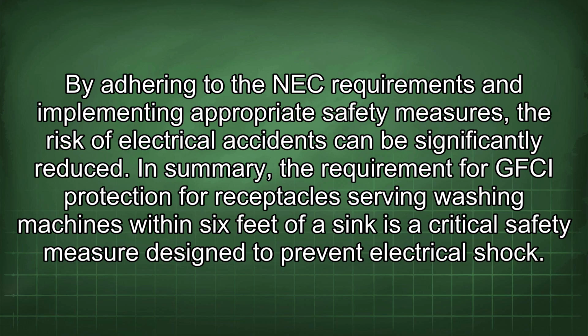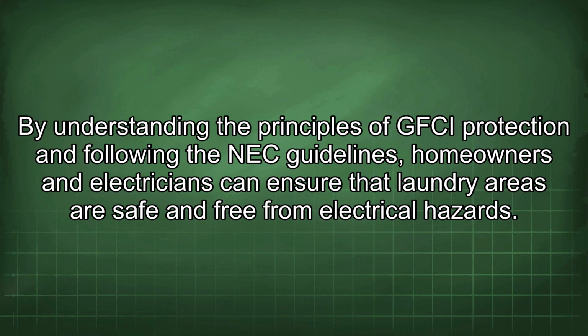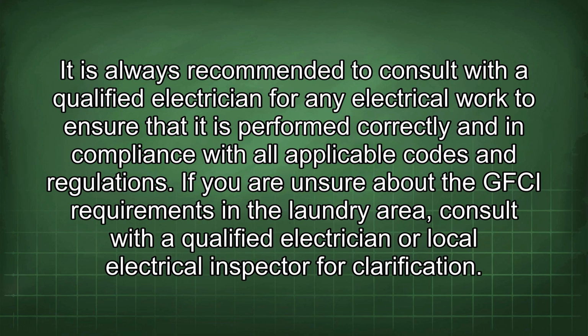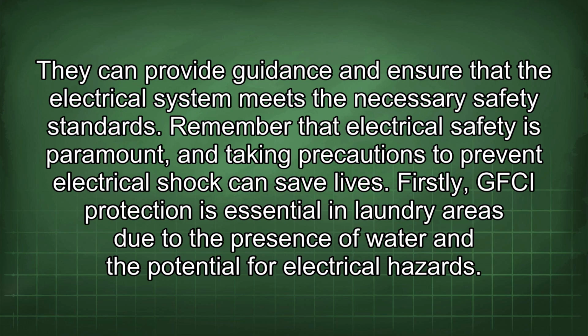In summary, the requirement for GFCI protection for receptacles serving washing machines within 6 feet of a sink is a critical safety measure designed to prevent electrical shock. By understanding the principles of GFCI protection and following the NEC guidelines, homeowners and electricians can ensure that laundry areas are safe and free from electrical hazards. It is always recommended to consult with a qualified electrician for any electrical work to ensure that it is performed correctly and in compliance with all applicable codes and regulations. If you are unsure about the GFCI requirements in the laundry area, consult with a qualified electrician or local electrical inspector for clarification. They can provide guidance and ensure that the electrical system meets the necessary safety standards.